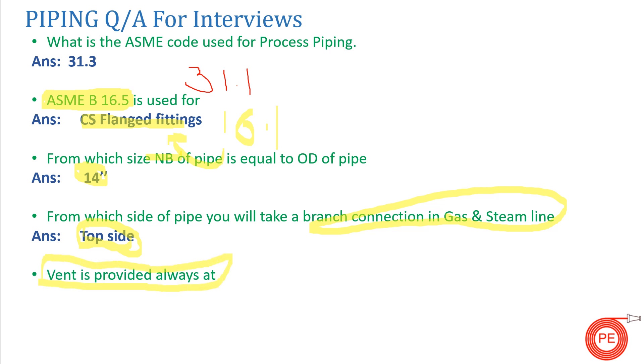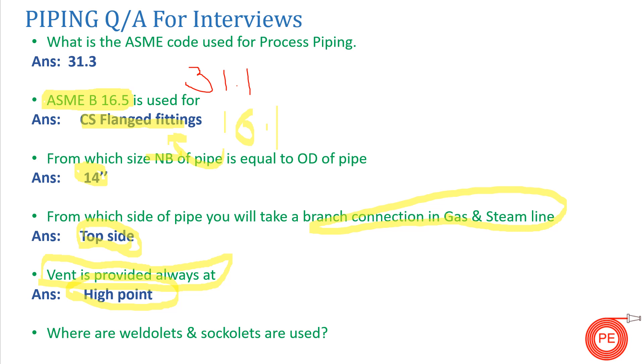Why is a vent provided? A vent is provided to remove gases or air while testing at the time of commissioning. The location of the vent — where is it provided? The vent is always provided at the highest point, so there is no gas entrapment, and while purging is done everything within the pipe can be removed.